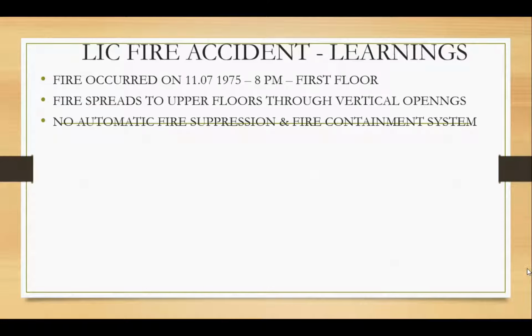And there was no automatic fire suppression and fire containment system. So there is no fire suppression. Even if the fire suppression fails, the fire must be contained in the place of origin itself by having fire resistant compartment walls and fire doors, so that even if the sprinkler system fails to suppress the fire, the fire will burn itself in the same place of origin and will not pass on to the next compartment, so that fire will not spread and people can evacuate easily. So that is the purpose of fire containment, but this automatic suppression system and fire containment system were not provided there.